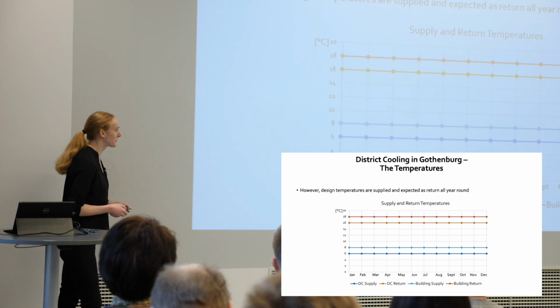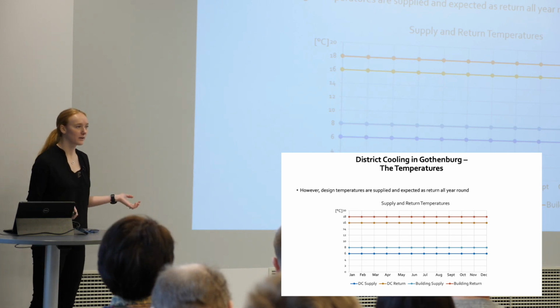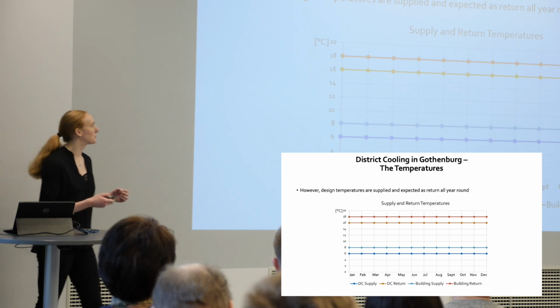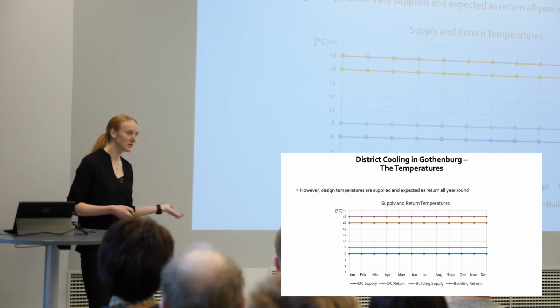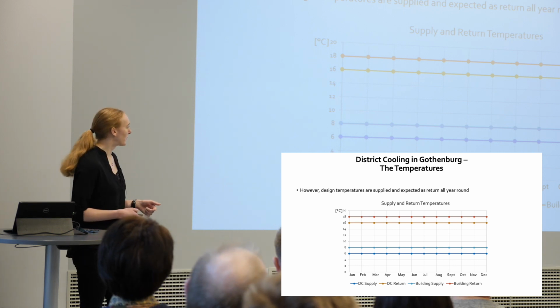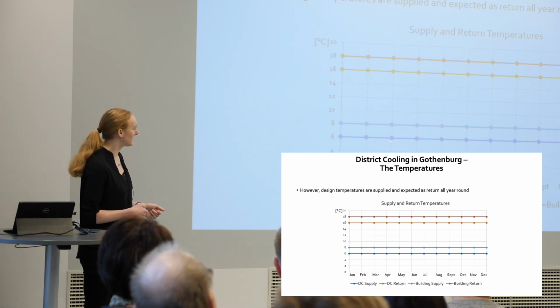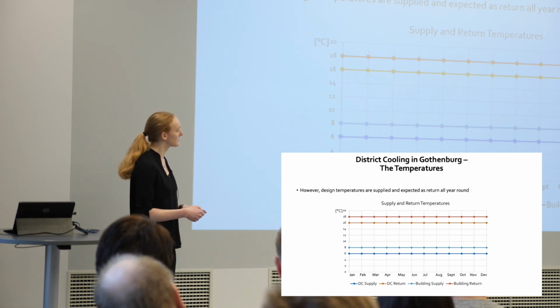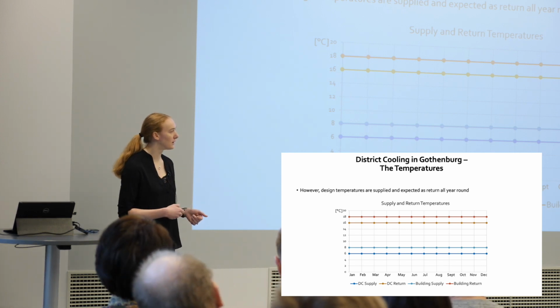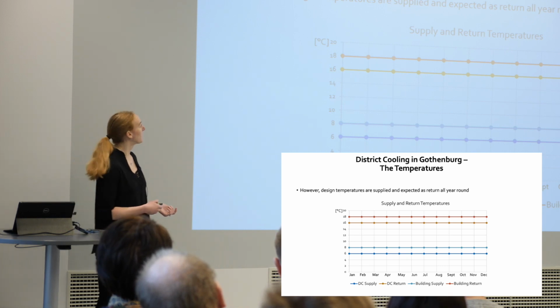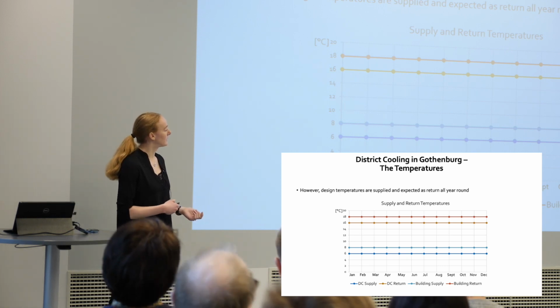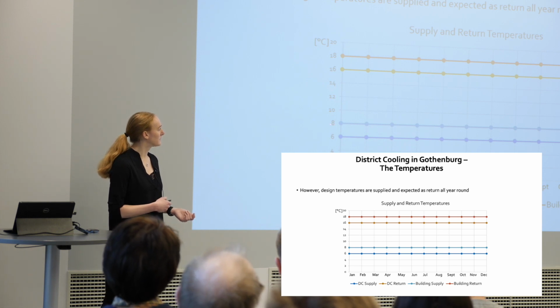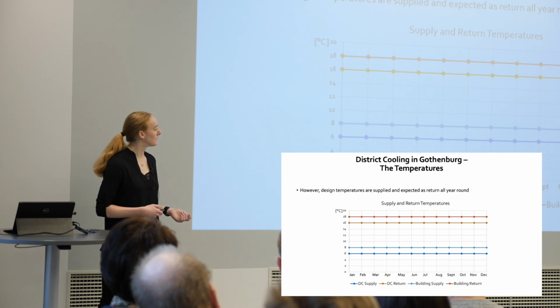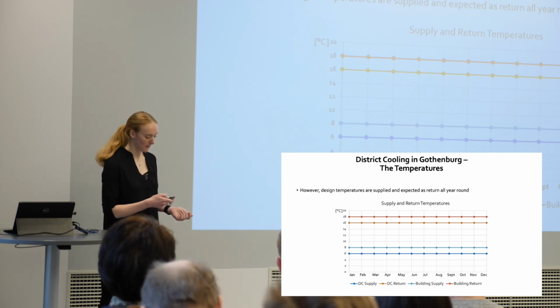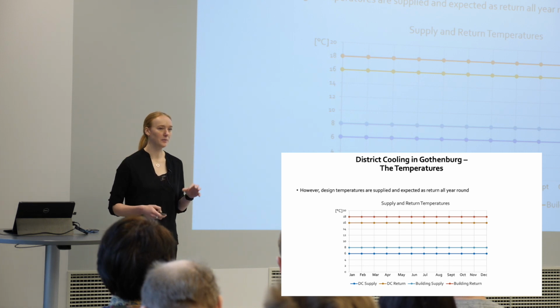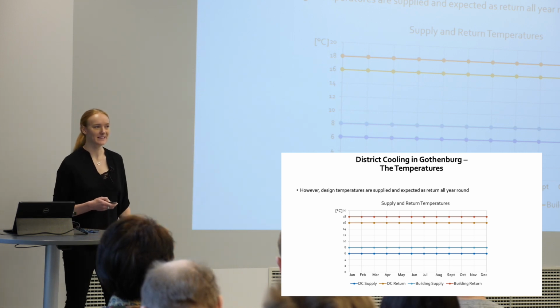However, these temperatures are the same throughout the whole year. There's no variation depending on the outdoor conditions or the cooling demand of the building. So the utility, Gothenburg Energy, they supply 6 degrees throughout the whole year, more or less. They go down a bit lower in the winter if the river is colder. And they want 16 degrees back all year round. And with that, they also expect building owners to use 8 and 18 all year round. However, there are some ranges allowed, but these are the bottom baseline temperatures, so to say.